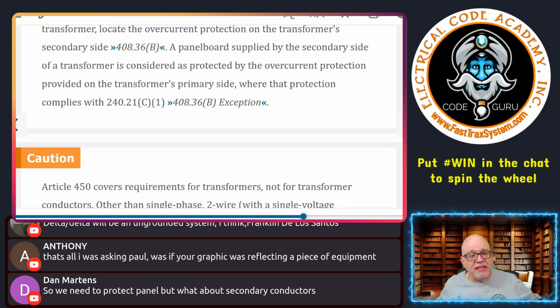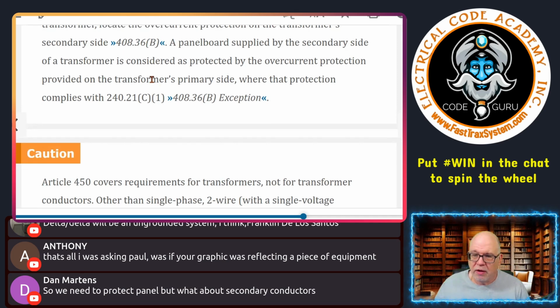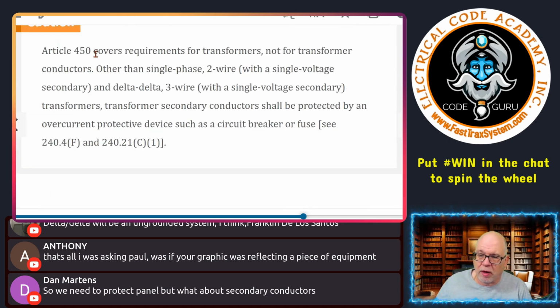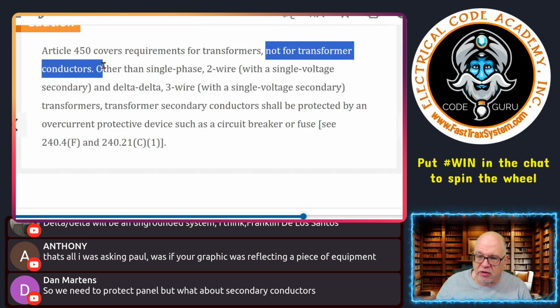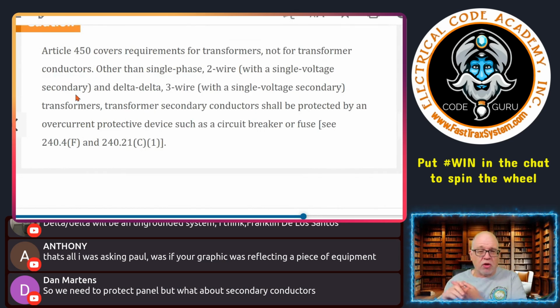So that is a very unique situation where you would not have to have the protection in the panel board because it's protected on the primary side. Very unique scenario, okay? Caution. Article 450 covers requirements for transformers, not for transformer conductors, okay? So all we're talking about right now is just protecting a transformer. That's it. That's the only protection we're talking about.